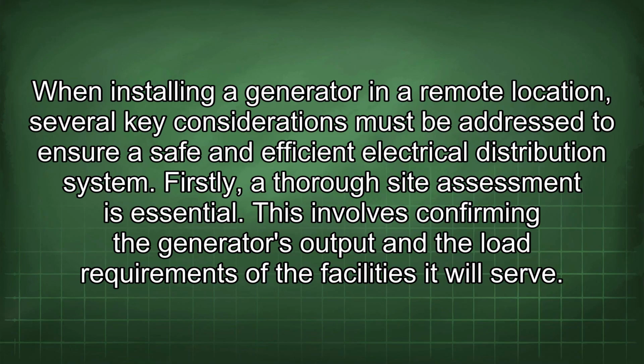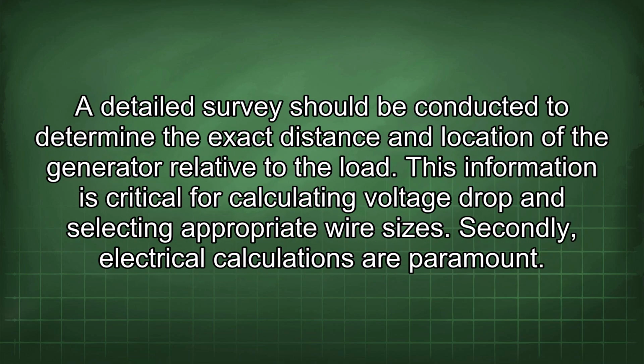When installing a generator in a remote location, several key considerations must be addressed to ensure a safe and efficient electrical distribution system. Firstly, a thorough site assessment is essential. This involves confirming the generator's output and the load requirements of the facilities it will serve. A detailed survey should be conducted to determine the exact distance and location of the generator relative to the load. This information is critical for calculating voltage drop and selecting appropriate wire sizes.